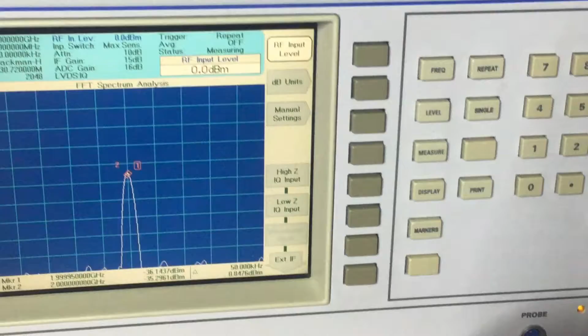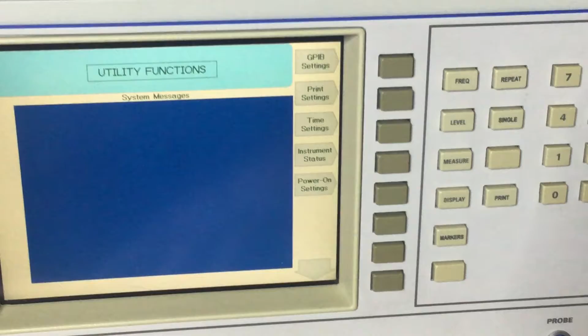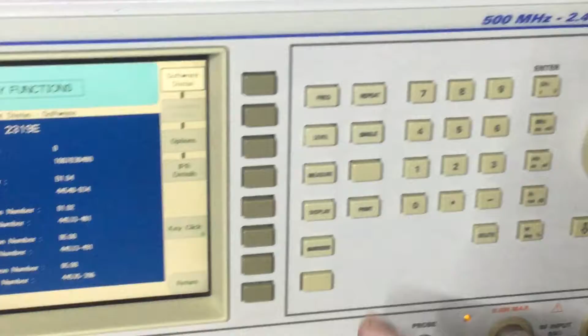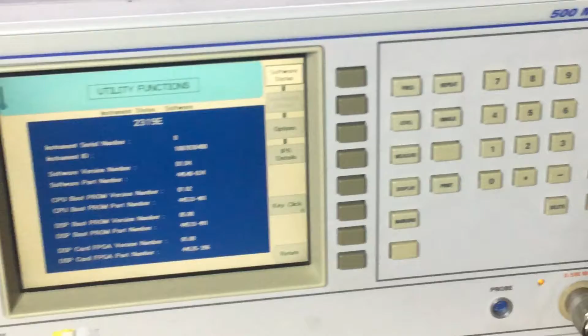So what I've done as well on this, just to see if there's a calibration error, I went into the utils function here, and I went into the calibration menu. I think it's under instrument status somewhere, there was a calibrate menu I went into, and I found what the code was to get into the calibrate menu just by messing about, and I tried to recalibrate it using my reference signal generator, just to see if the calibration data was lost and it just needed recalibrating, which is a reason for the level obviously not reading correctly. But just seeing if I can find it now.